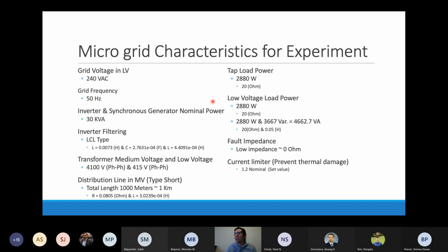So we test tap load. We will also test low voltage load power. We will test different fault impedances. In our case, I will just show the 0 ohm impedance, which is when we have an event that happens in the grid, and we will contrast this with the different types of power introduced to the grid. And for the limiters that we defined previously, we are utilizing 1.2 based on the literature. That is a nominal point to prevent the inverter from having thermal damage.